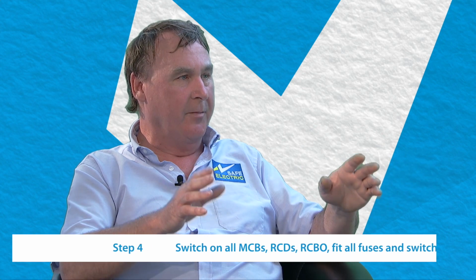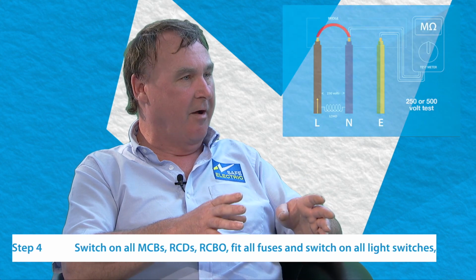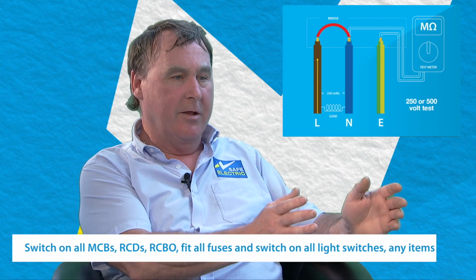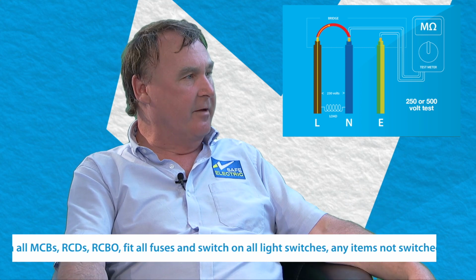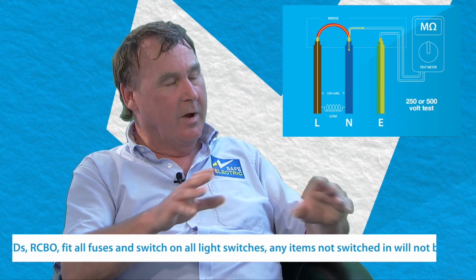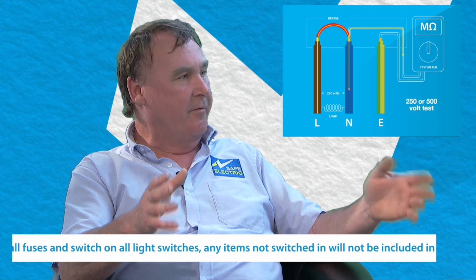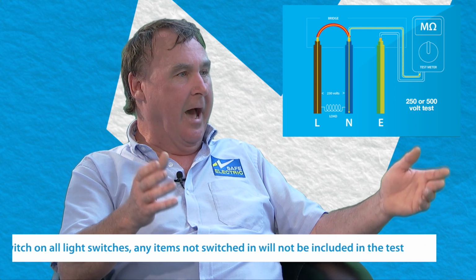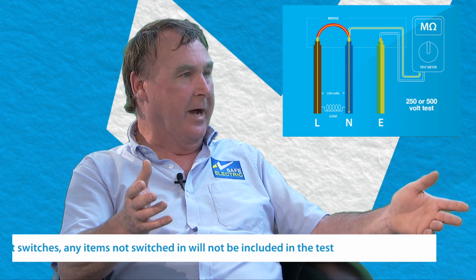And the last very important step is to switch on all MCBs, all RCDs, all RCBOs, switch everything on in the installation, including all your light switches. You can then do a test at the lower voltage I would recommend, 250 volts to start off with, between all your live conductors and the protective conductor. That will give you an overall insulation reading for the entire installation, and anything greater than 1 megaohm is a pass.